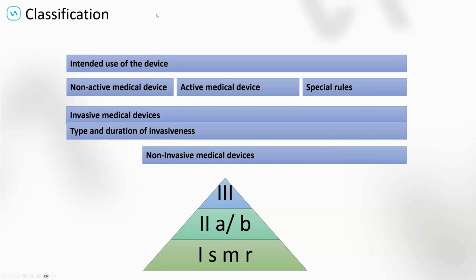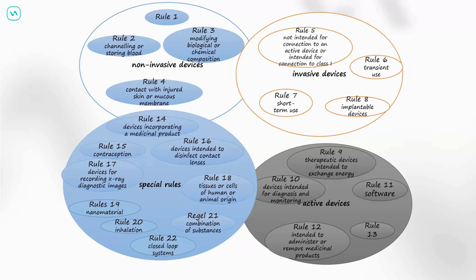So whenever you now know your intended use, you know your principles of operation, you know if it's an active or a non-active medical device, and that already excludes you from a set of rules. However, the set of the special rules always applies. So going through the rule set, if you have a non-active medical device, you start in the left upper corner with non-invasive devices. Then you go into the invasive devices, depending on whether your device is invasive or not, and you go into the special rules for non-active devices. If you have an active medical device, you need to include the list of the active medical device rules as well. So you have rules 9 to 13 also to be taken into account. And that is a bit of a difference in that rule set. So if you're a non-active device, you can skip those rules. If you are an active device, you need to run through all the rules and find the one which is the highest classification for you.